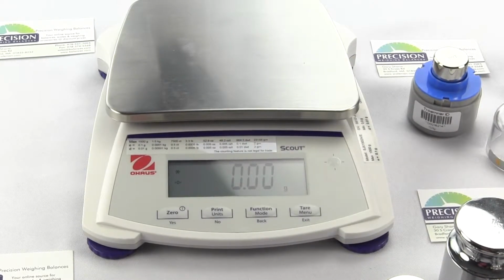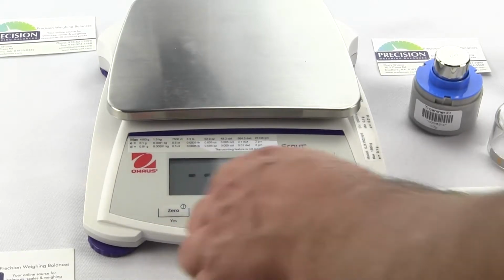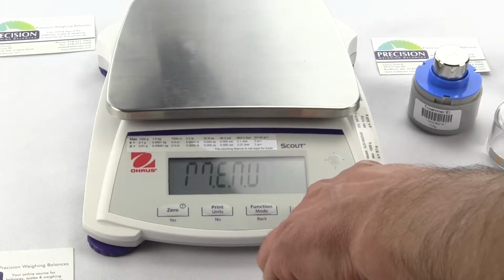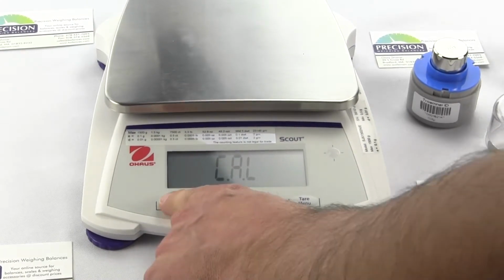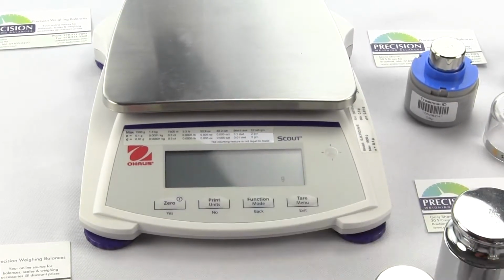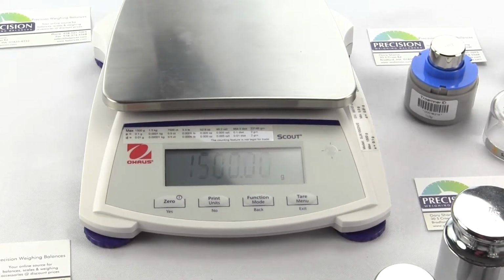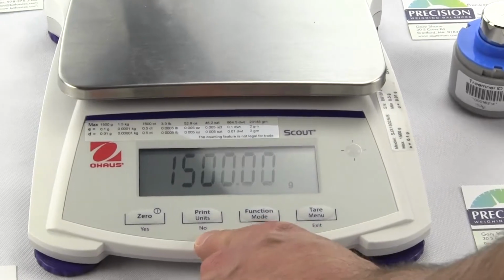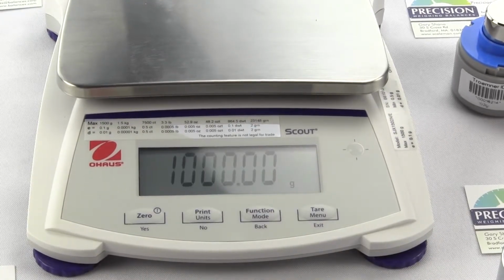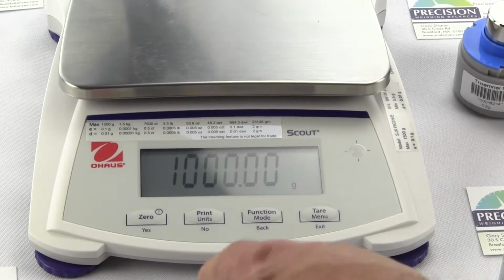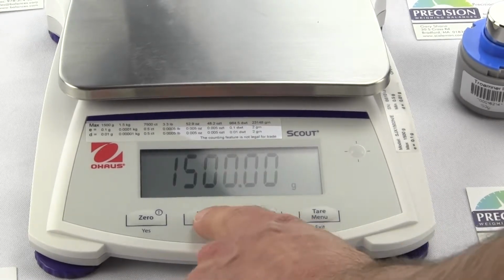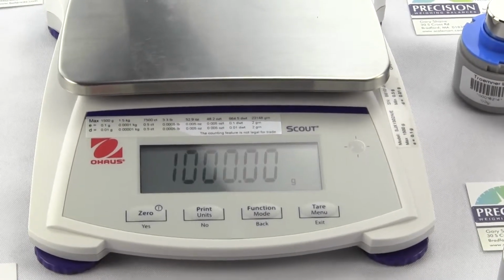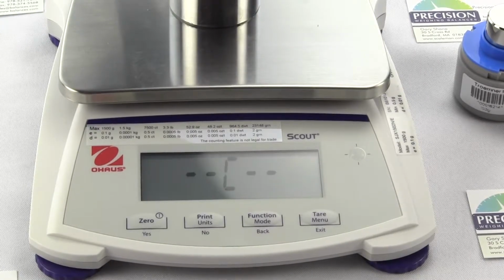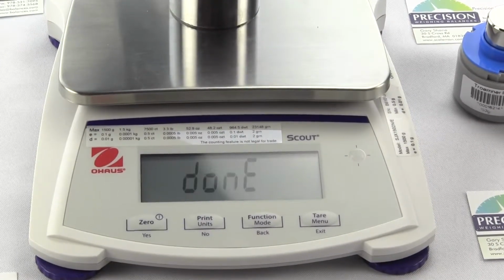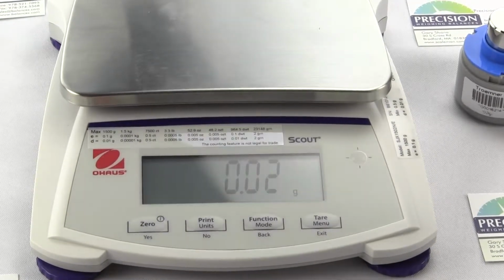Now we'll do the span calibration again, this time with 1,000 grams. So again, it says cal. We press yes. We want span. We hit yes. It shows 1500. This time we don't want to use 1500. We want to use 1,000. So we're going to hit no, and it goes to 1,000. You only have a choice of 1,000 or 1,500. So we want 1,000. It flashes 1,000. This time we're going to take the 1,000 gram weight and put it right on the center. You'll see the dashes with a C, meaning it stored the value. It's done. It returns back to the weigh mode.